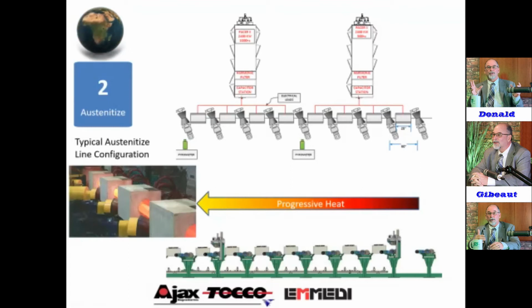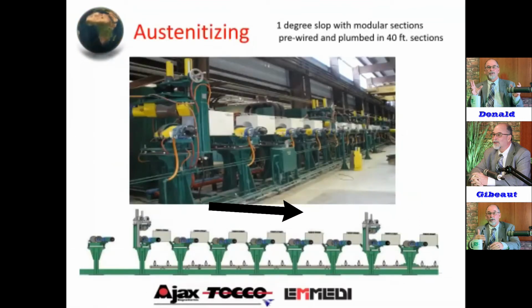A lot of our lines, most of our austenitizing lines, are built on a 1 degree slope, so that any quench water on our very aggressive quench, if there are any gaps and it gets into the inside, because it's not a perfect seal by any means, and we're really throwing the coals to it on pressure somewhere. We have lines running at 7 to 10 psi on the individual circuits on the quench, going up to 35 to 40. So the 1 degree slope helps us keep water from going back up into the coils. And when you're heating the pipe to 1850 degrees, water spraying on the inside is going to thermal shock and break the alumina refractory out. So here's a typical line. This one is rated at 36 tons an hour.